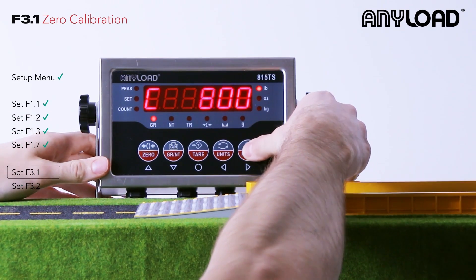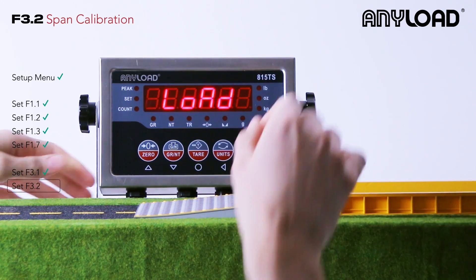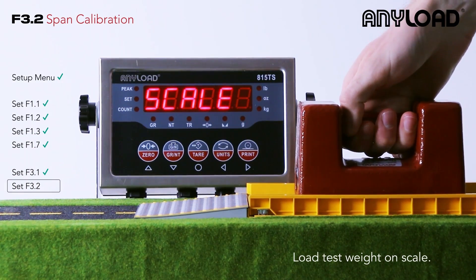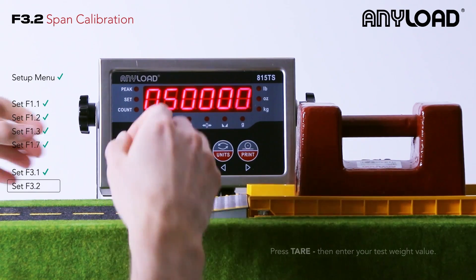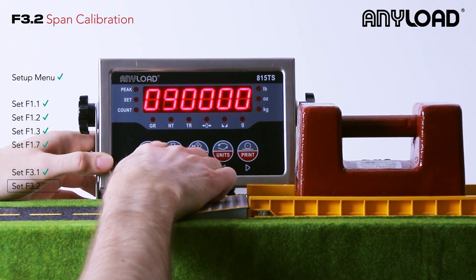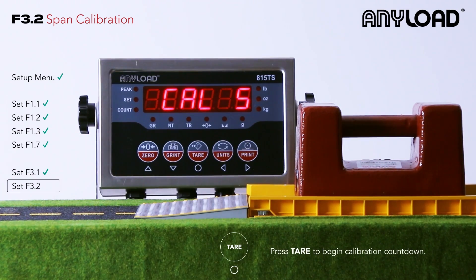Once that's complete, we're going to go directly to our F3.2 setting, which is our span calibration. It's going to ask us to load our test weights on the scale. Once that's complete, we're going to press tare and it's going to ask us for the value of that test weight. In this case we're going to say this is 50,000 pounds. Press tare to enter and you'll get your calibration countdown from five.